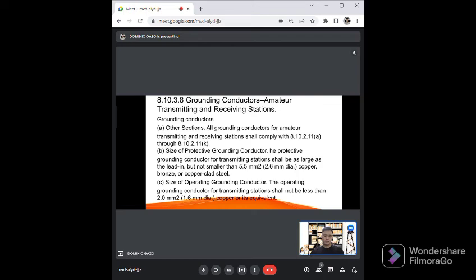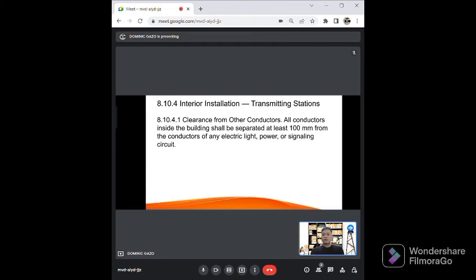For interior installations, transmitting stations, for this article, all conductors inside buildings shall be separated at least 100 mm from the conductors of any electrical, light, power, signaling circuit.